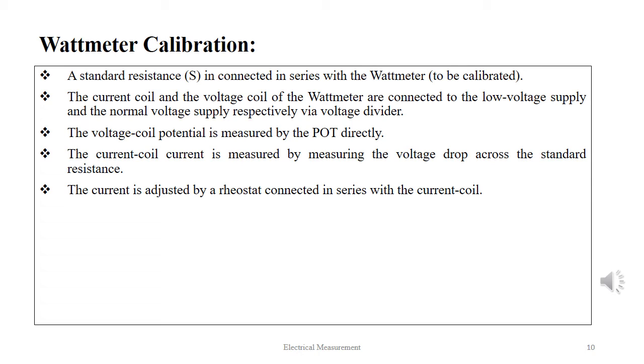Wattmeter is the device that measures the power consumed in the circuit. Here, just like the ammeter, a standard resistor is connected in series with the wattmeter, which is under calibration. It comprises two coils, the current coil and the voltage coil, and the current coil is connected to the low voltage supply and the voltage coil to the main or the principal voltage supply respectively by a voltage divider. The voltage coil potential is measured by the pot directly. The current coil current is measured by measuring the voltage drop across the standard resistor S. The current is adjusted by a rheostat connected in series with the current coil.